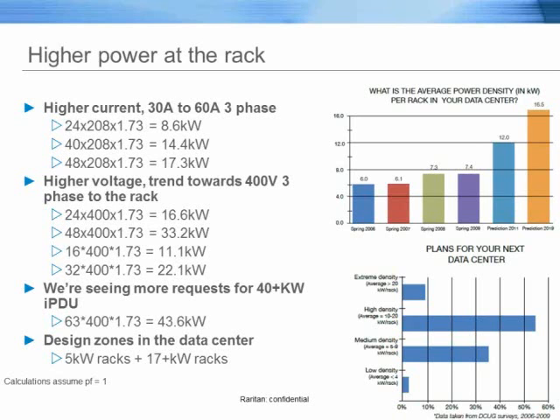And we are seeing customers that are delivering that much power to the rack. Again, with blade servers, with consolidation, we've seen customers actually do custom-built 50, 54U racks. With cooling technology increasing too, the data center can handle these new high-power loads. We're seeing a lot of customers deploying liquid-cooled racks, spot cooling, chimney systems, outside air economization. So with this new increase in cooling capacity, the ability to deploy a 16.6 kW rack is feasible, it's doable, and people are doing it. So three-phase power is phenomenal. Now if we can bring it up to 400 volt three-phase, true high power to the rack, it really gives us a lot of benefits. We can deploy that much product, we can deploy that much power, and we know that power is there for future usage.